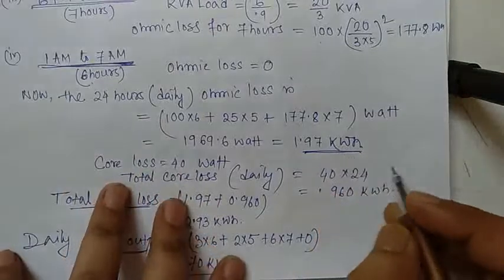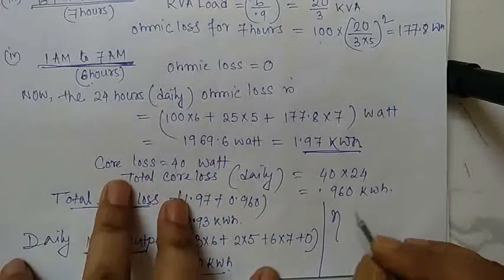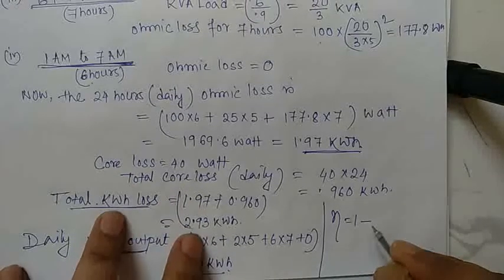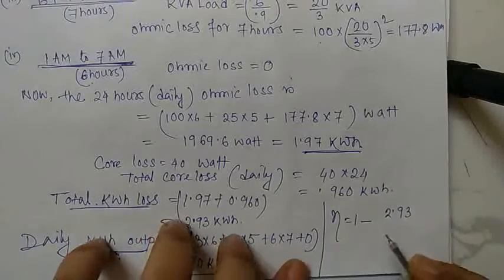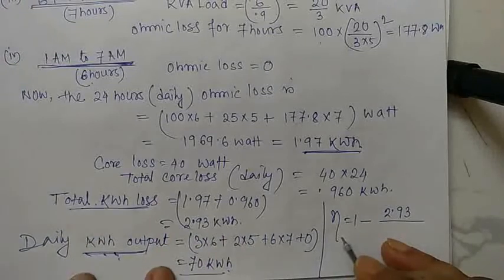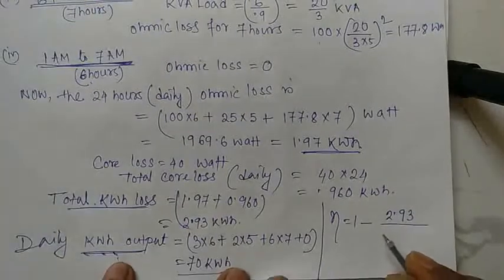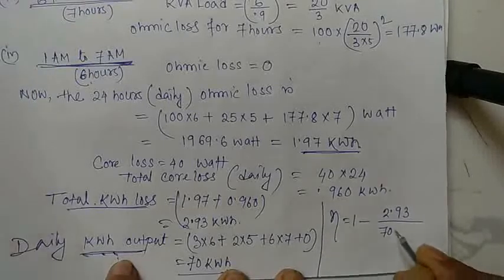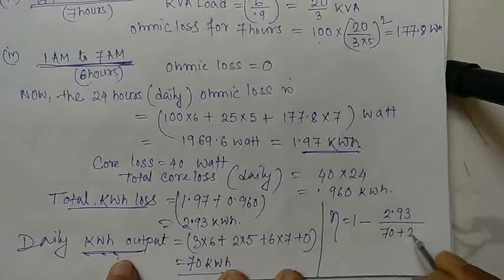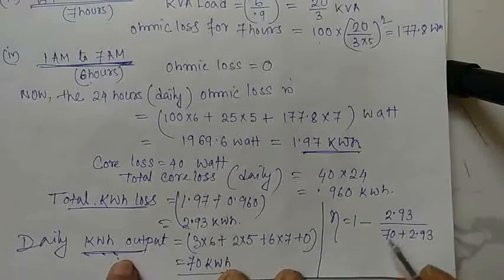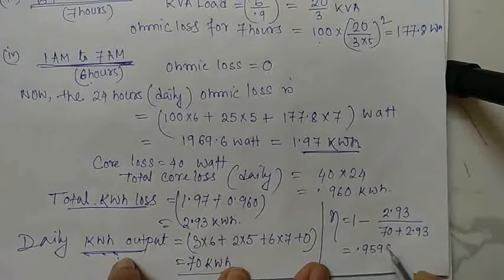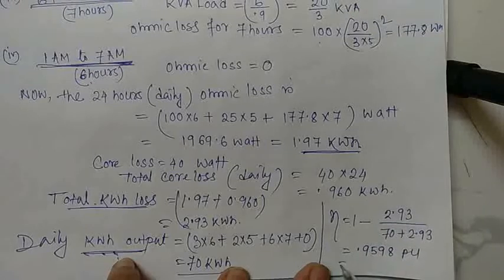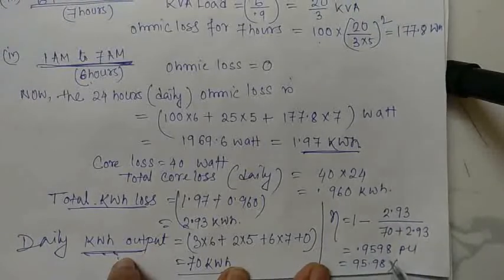The all-day efficiency equals 1 minus losses divided by input. Losses are 2.93 kWh, output is 70 kWh, and total input is 70 + 2.93 = 72.93 kWh. So efficiency = 70 / 72.93 = 0.9598 per unit, or 95.98 percent.